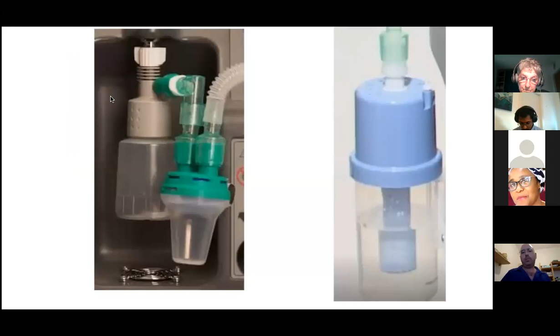Okay, after we turn the machine on and before we connect it to the patient, we need to check that the machine is working properly, so that when we connect it to the patient it will help them and not interfere with his or her work of breathing. How do we do that? We need to check for bubbles. We look at all the tubes. We occlude the prongs with our hand and check for bubbles. Where do we check for bubbles? The bubbles will indicate that we have enough flow and enough pressure. We check for the bubbles in the CPAP tank and the humidifier bottle.